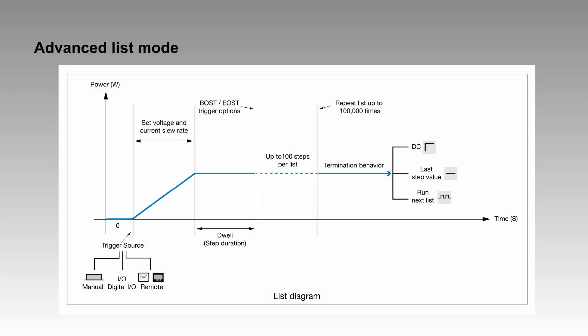List mode is useful for repetitive testing and applications requiring a specific sequence of output levels. User-configurable voltage, current, and dwell time can be set for up to 100 steps in a list.